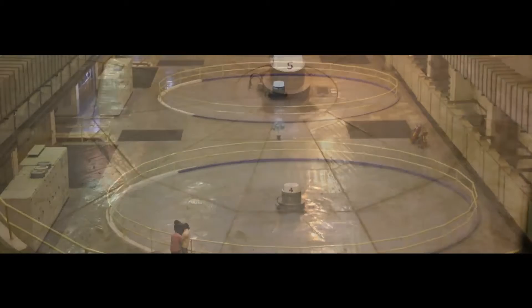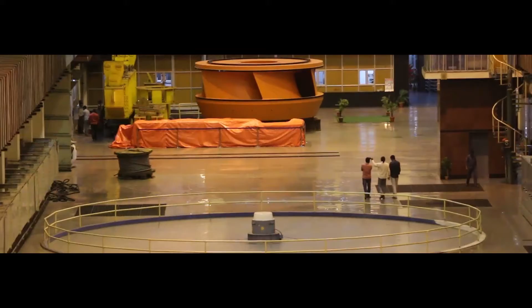Advantages of this powerhouse are that the units are designed to increase the generation to full output capacity even in 1 minute or even less. The plant load factor of thermal power stations can be improved by providing demand to the power system during night time by taking pumping power. Units can be used as spinning reserves in the system, enabling finer frequency regulation. In addition to the above, these units can be operated as synchronous condensers for supplying reactive power and for meeting the increased peaking demands.